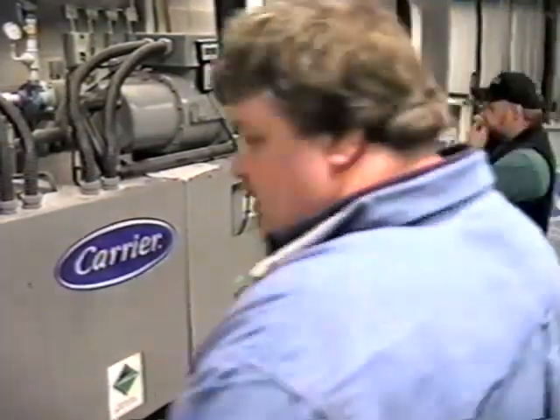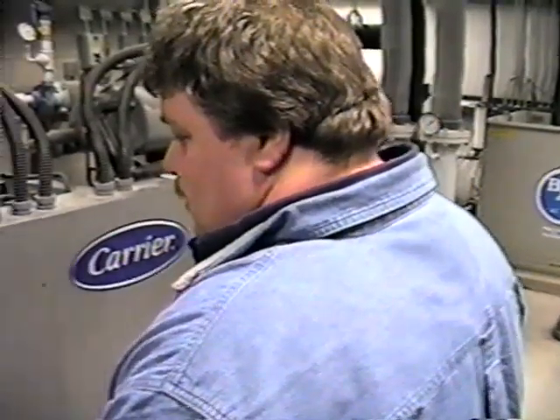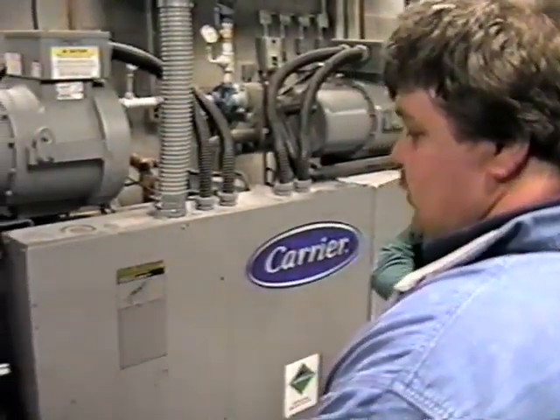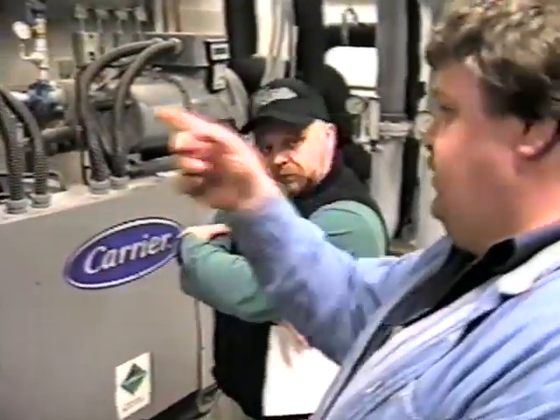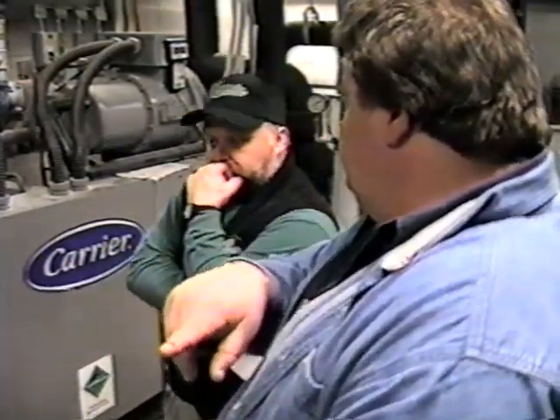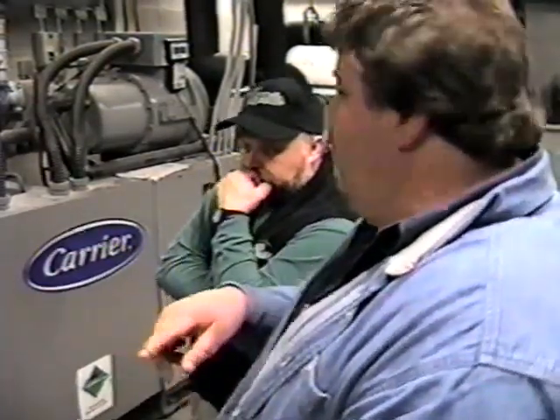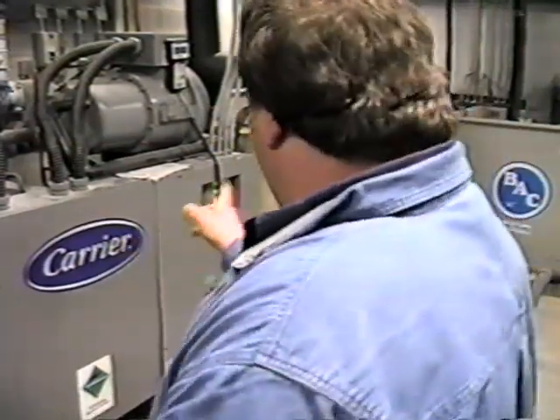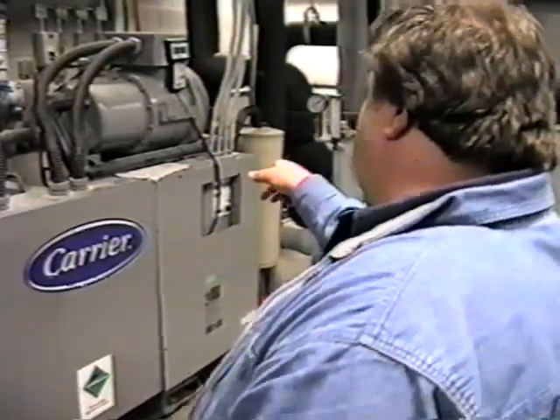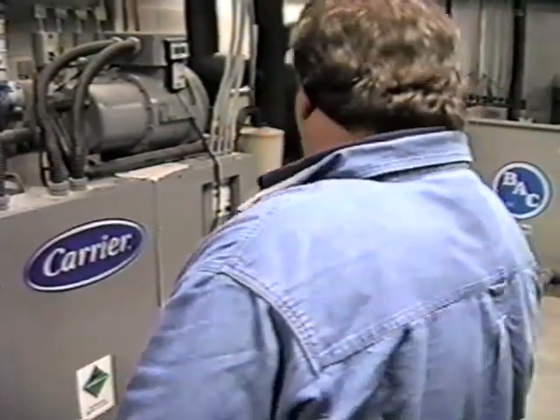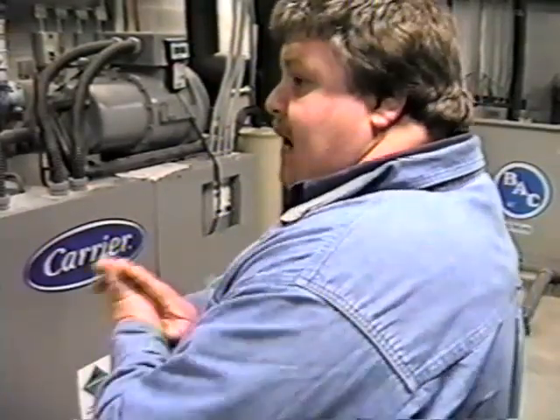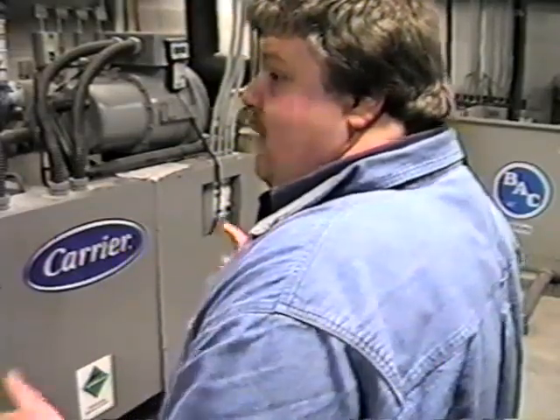I think that's pretty much it. We added the refrigerant alarm. If for some chance we felt that the smart drive itself wasn't working, what we can do is shut off pump number 1 and turn pump number 2 to the on position. That one will come right on at full speed, and then we'll switch the chiller over here into the local control. Okay. And we'll also have to set your set point up to a more normal temperature, 20 degrees or something like that, and then you'll be back to a basic system again. So you have a fail-safe no matter what.